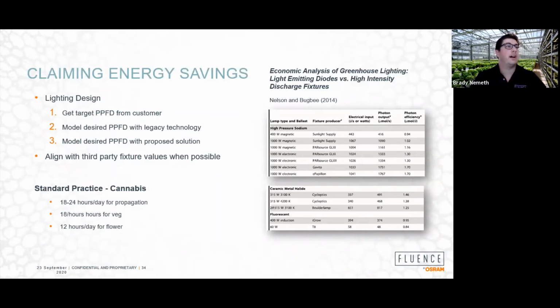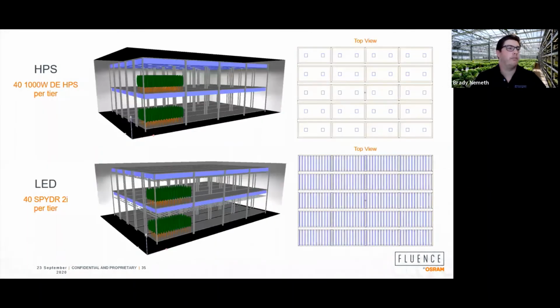So if you go to the next slide, we'll take a look at an example of a 2-tier setup where we might just model out the entire room. Occasionally, we'll just model out a 4x4, 4x8 rack when a racking system is in use. It saves a lot of time, and honestly there is no real additional value you get by modeling out an entire room of racks versus a single rack to prove out the ratio of legacy technology to proposed.